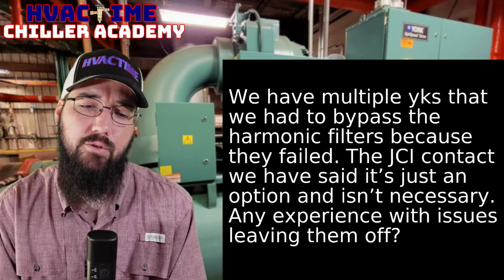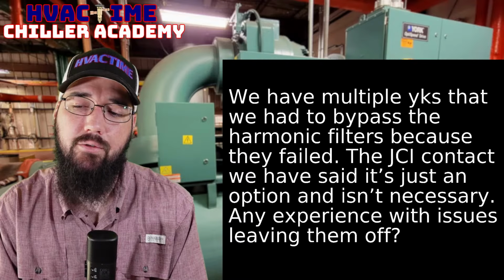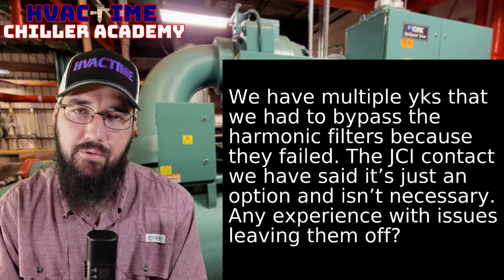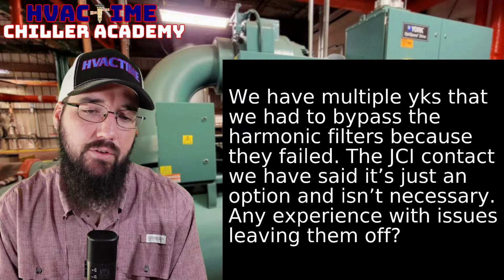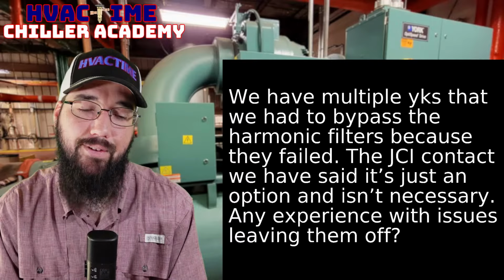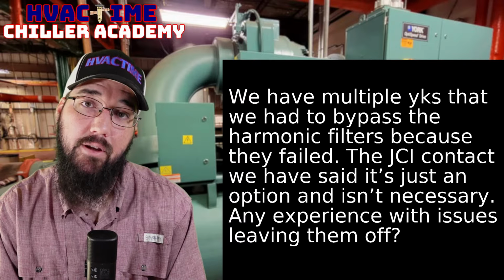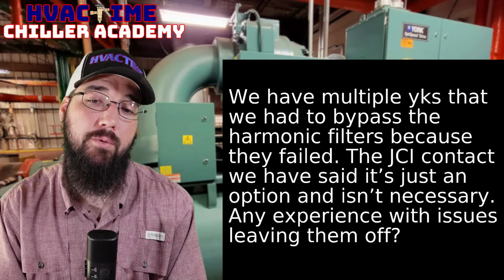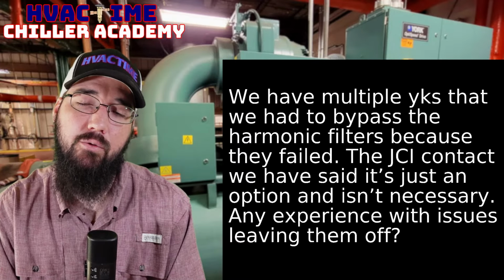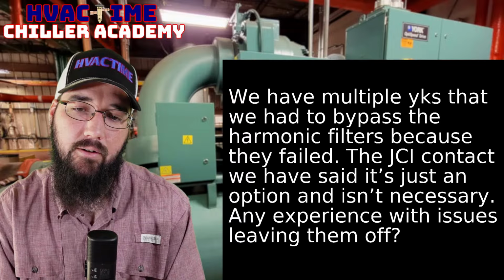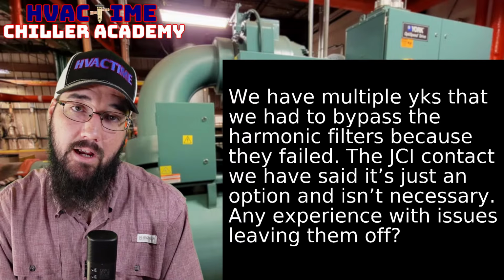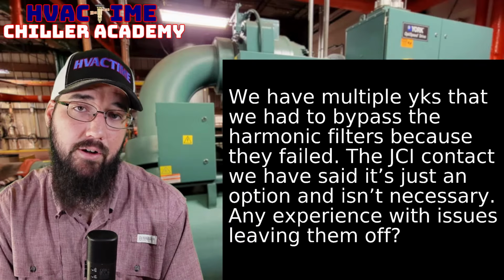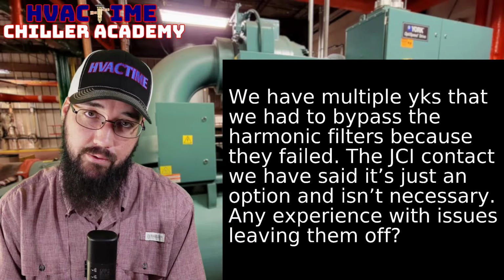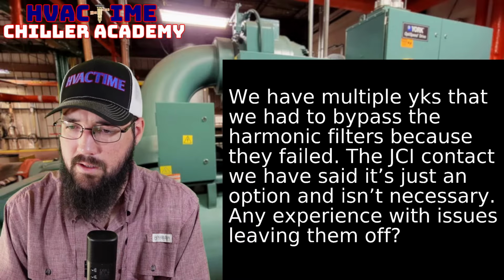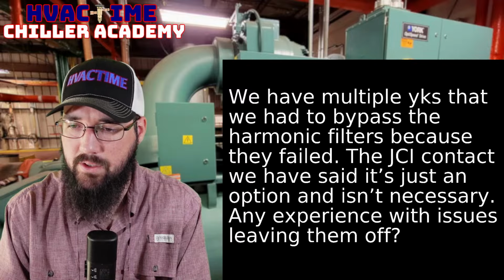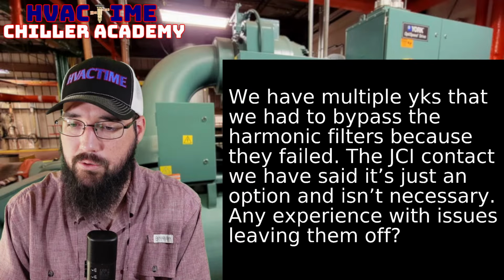Anyway, to just very specifically finish, as long as you're running through your inductor, your line filter, and that hasn't been bypassed, you're perfectly fine. And if it did get bypassed, I would highly recommend adding that back. And I would assume that JCI is thinking that, well, you can remove the harmonic filter components, but the line reactor is technically a primary drive component, not a harmonic filter component. Just bear that in mind. We had a 19XR in that same room that blew the line reactor soon after.